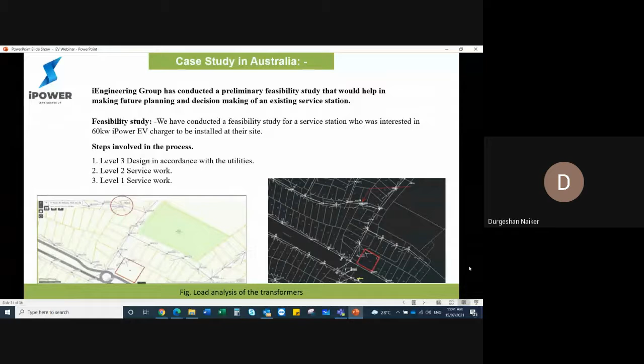But in this particular case study we did, the client was lucky. In other words, the study showed that the transformer was not fully loaded. It had capacity to supply 60 kilowatts, and the conductor did not need to be upgraded. So we figured out that it is pretty much only on-site work that has to be done, not on the utility side, but from the meter to the client side, which only required some modification.